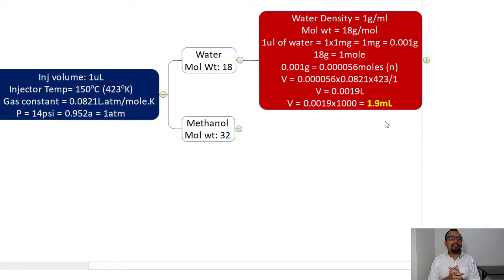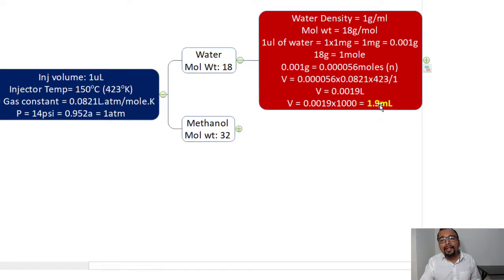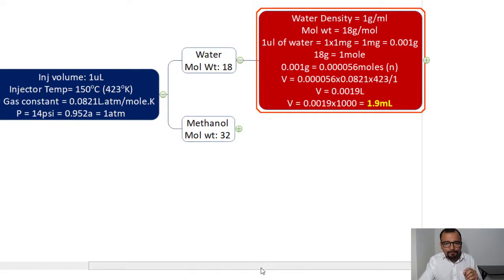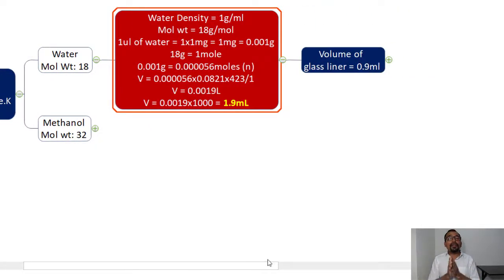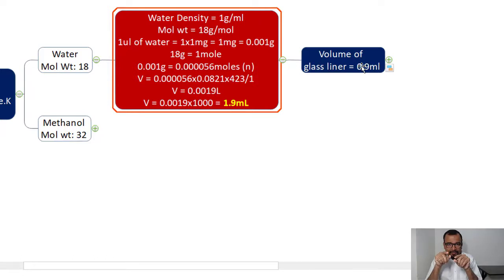So this means that once you inject 1 microliter of a water-based sample solution at 150°C and around 1 atmosphere pressure, it is going to expand to 1.9 mL. If your glass liner volume is only 0.9 mL, that is not sufficient to occupy the 1.9 mL of water vapor, and you can certainly expect a back flash.